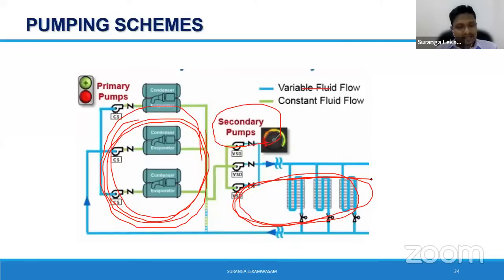So what's the balance? You need a connector between these two loops to balance the flow rate, to bypass between primary and secondary. This is called the decoupler, which will do the decoupling of the primary side versus the secondary side. So that's mainly about primary and secondary. Why were these primary pumps constant?